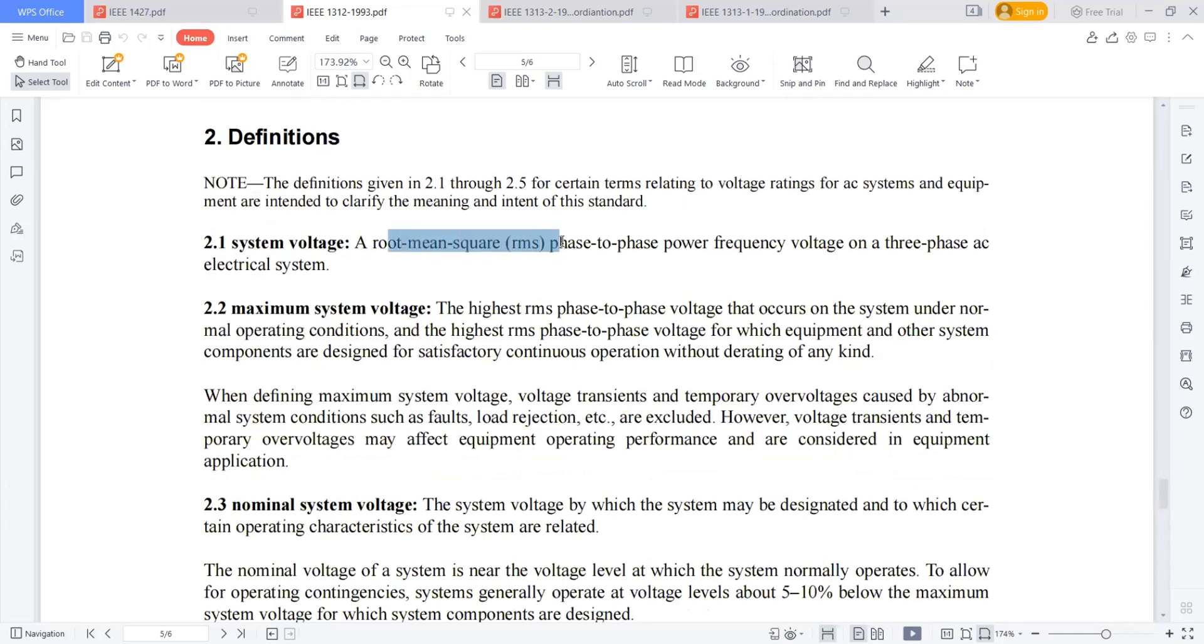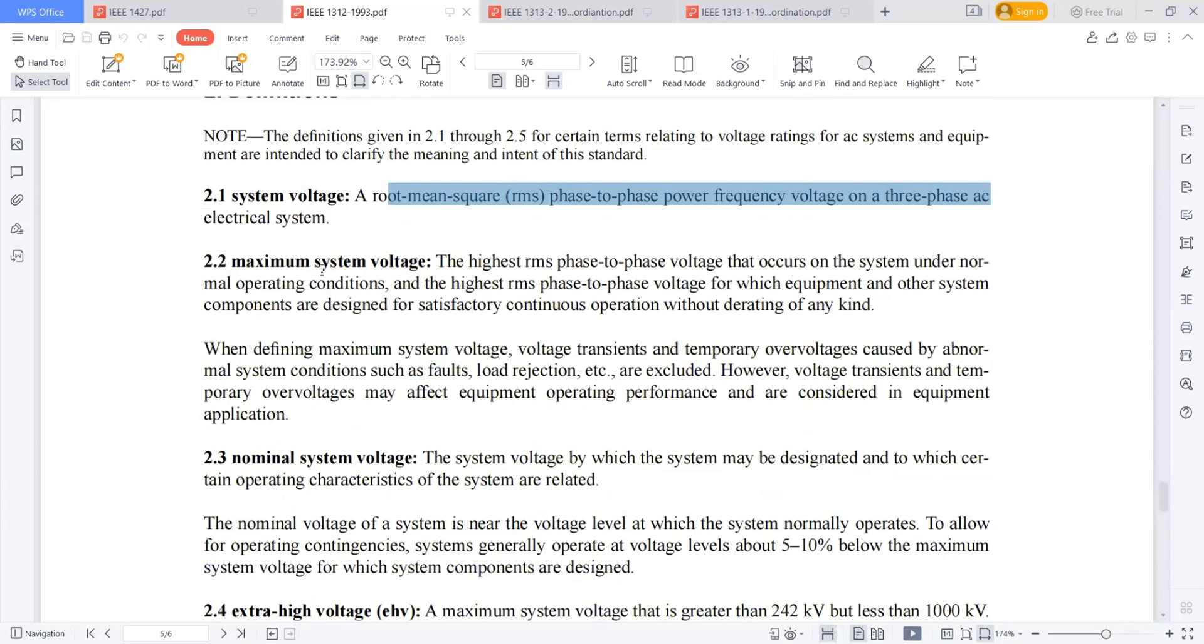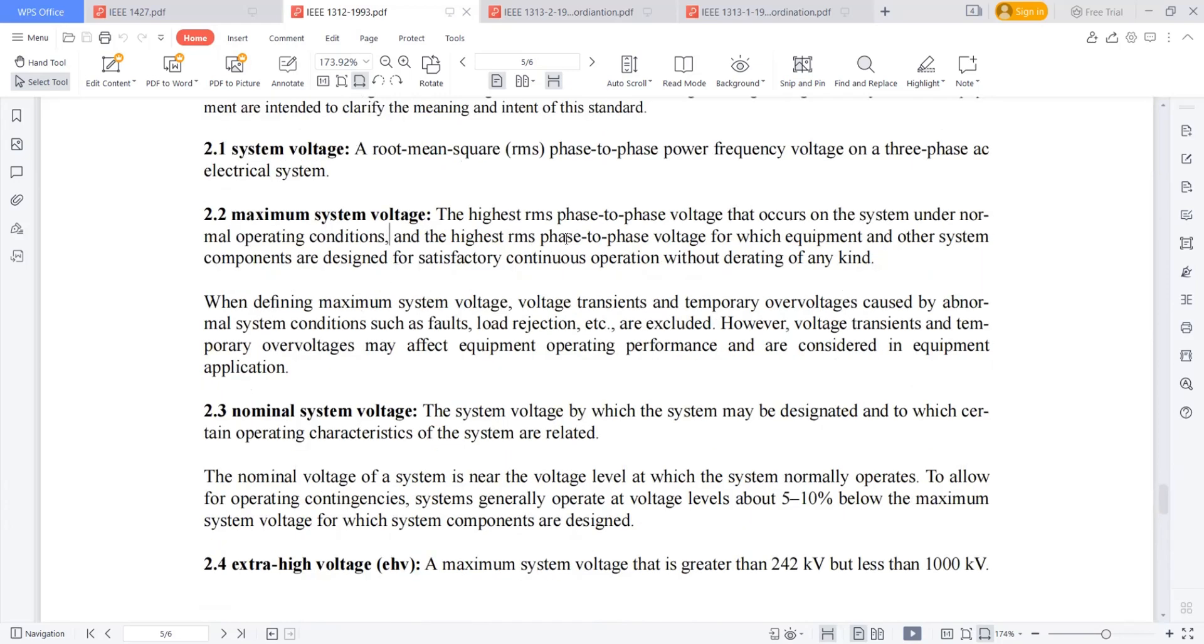The system voltage is the RMS phase-to-phase power frequency voltage on a three-phase AC network system. What is my maximum system voltage? The highest RMS phase-to-phase voltage that occurs on the system under normal operating condition, or the highest RMS phase-to-phase voltage for which equipment and other system components are designed for satisfactory continuous operation without derating of any kind.